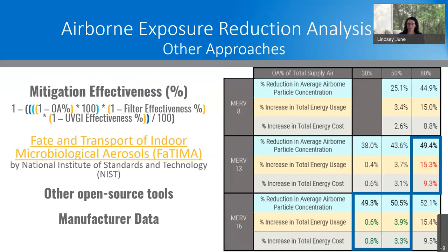So what they found was the ASHRAE recommended scenario produced a similar particle concentration reduction as the MERV 16 with 30% or 50% outdoor air, but with a much lower energy use and cost impact. And then there were other consultants that used other open source tools and or relied solely on manufacturer reported effectiveness or EACH. So on to the results, next slide.